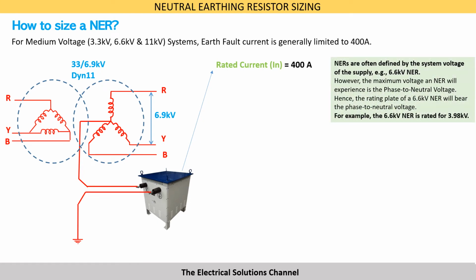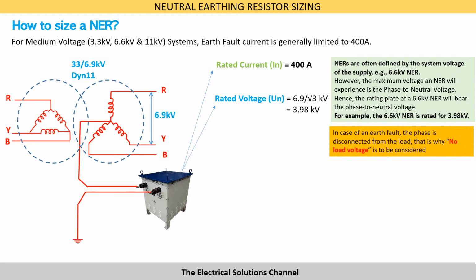NERs are often defined by the system voltage of the supply. For example, 6.6 kV NER. However, the maximum voltage an NER will experience is the phase to neutral voltage. Hence, the rating plate of a 6.6 kV NER will bear the phase to neutral voltage. For example, the 6.6 kV NER is rated for 6.9 divided by root 3, which is equal to 3.98 kV. In case of an earth fault, the phase is disconnected from the load. That is why the no load voltage is to be considered while arriving at the rated voltage of the NER.